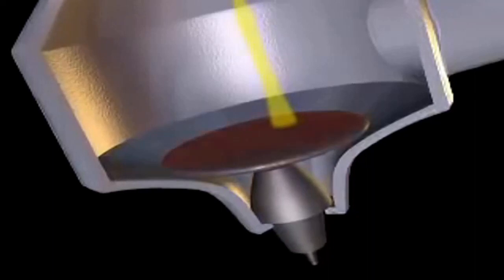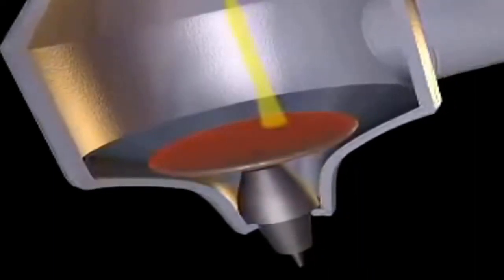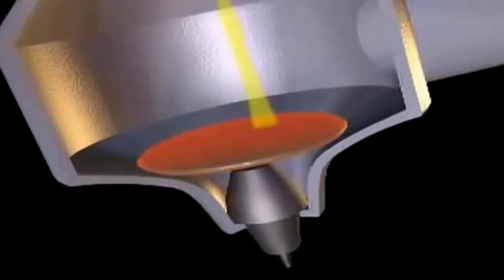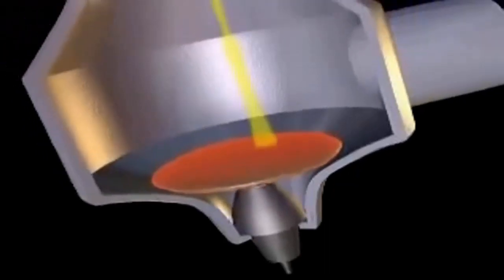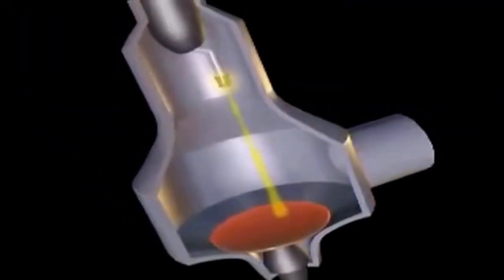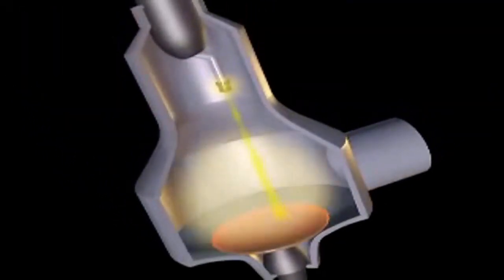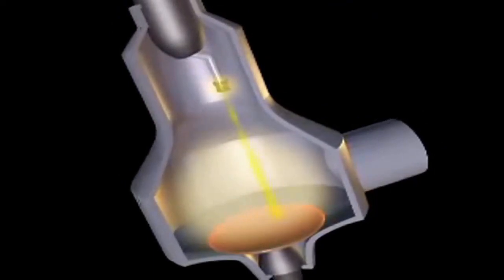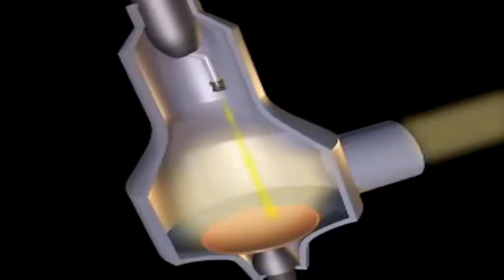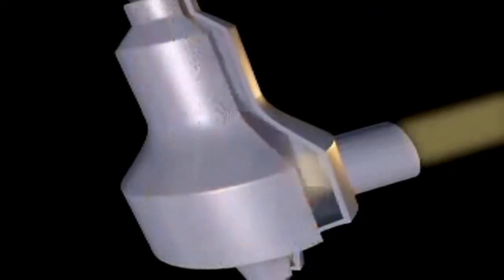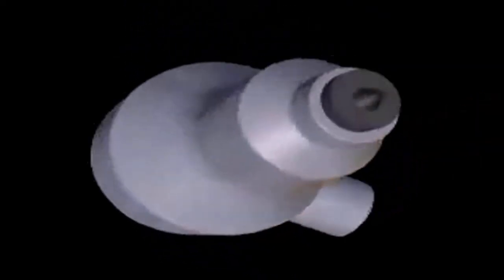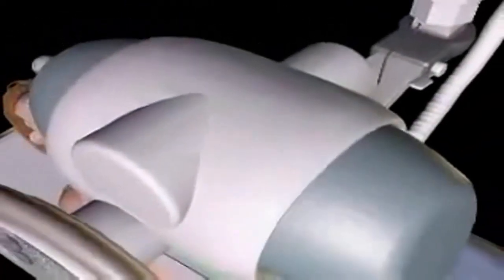The anode, located on the opposite end of the X-ray tube, is a disc made of tungsten, a material that attracts the electrons. When the electrons released from the cathode come in contact with the tungsten, they release energy in the form of photons. These highly energized photons are channeled through a lead cylinder and a series of filters, creating an X-ray beam.